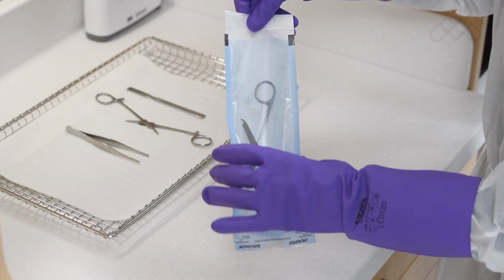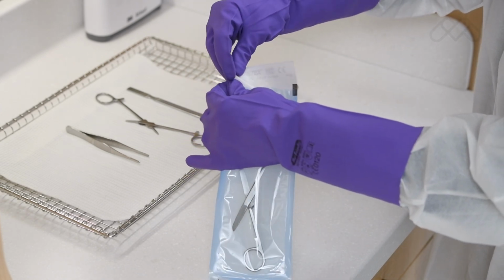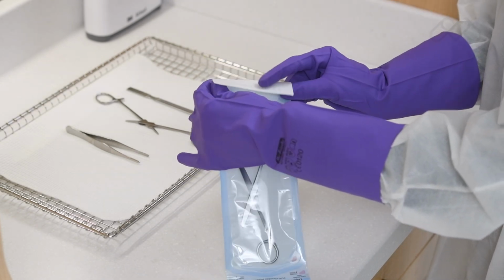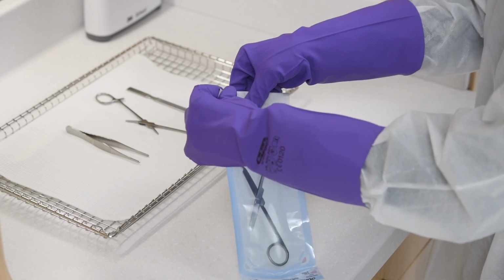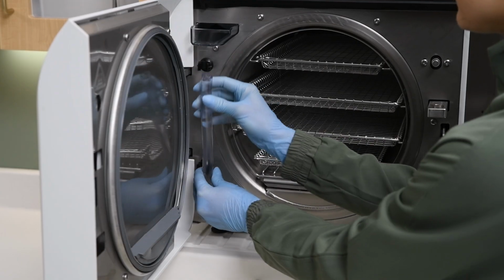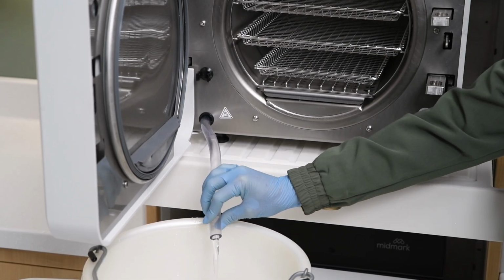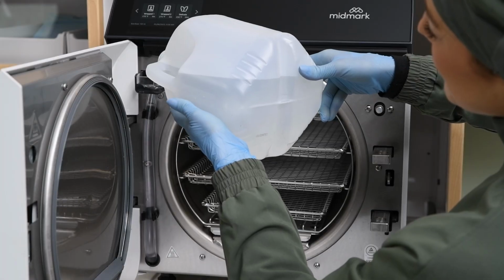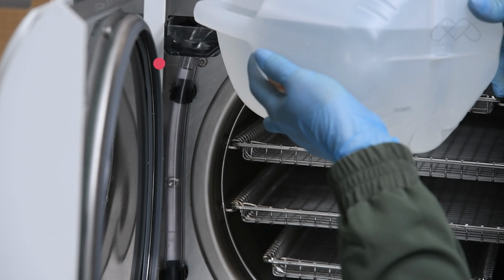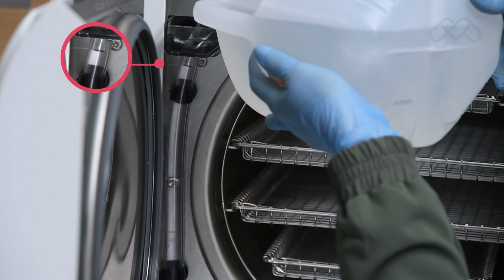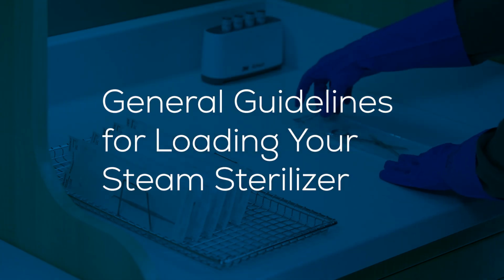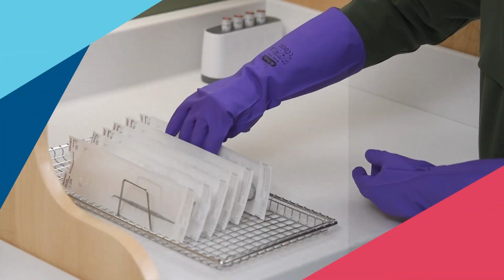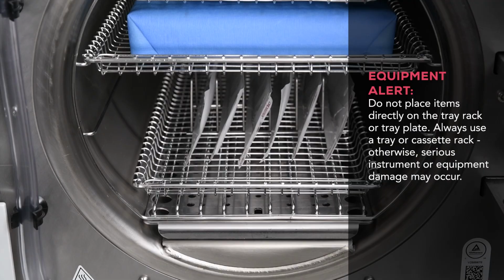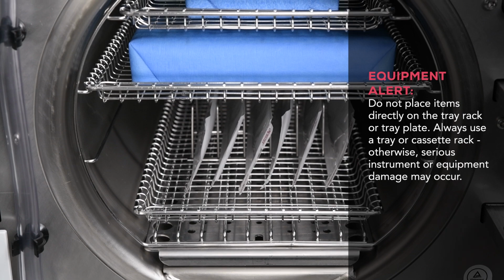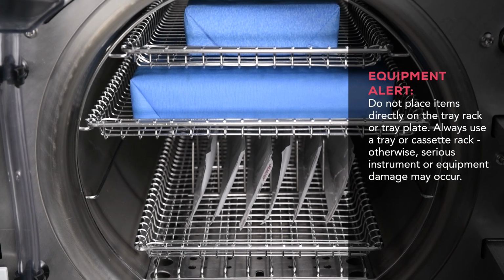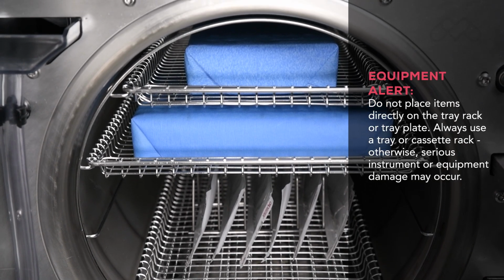Due to the sensitive nature of some types of surgery, instruments used in such procedures must be wrapped or pouched to maintain sterility and to be stored. The water reservoir should also be drained and refilled with fresh distilled water each day when processing instruments for these procedures on a routine basis. General guidelines for loading your steam sterilizer. Items to be sterilized should be arranged to permit free circulation of steam. Refer to general guidelines in the setup and user guide for examples of proper loading.